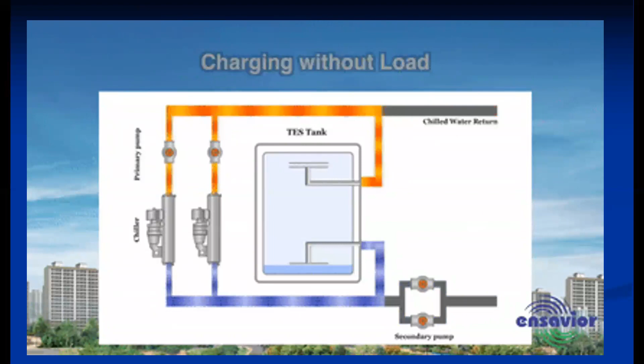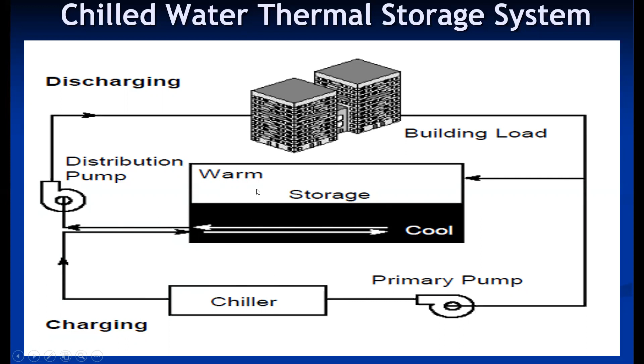But in this case, the chiller is not directly supplied to the building or the building load. The entire chill water is stored in the storage tank, and from the storage tank it is pumped to the building load, and the return line goes to the chiller, and only under the breakdown condition does the return line go to the storage tank. So that is the difference. Unlike the previous diagram, here the chiller is not directly connected to the building load. Via the storage tank it goes to the building with the help of pumps.